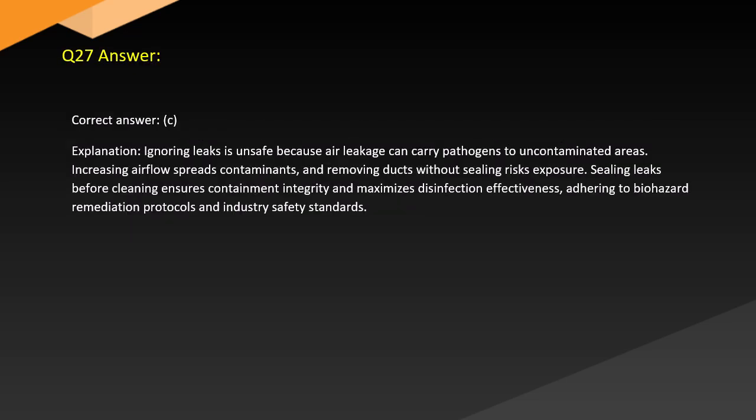Answer. Correct answer, C. Explanation. Ignoring leaks is unsafe because air leakage can carry pathogens to uncontaminated areas. Increasing airflow spreads contaminants, and removing ducts without sealing risks exposure. Sealing leaks before cleaning ensures containment integrity and maximizes disinfection effectiveness, adhering to biohazard remediation protocols and industry safety standards.